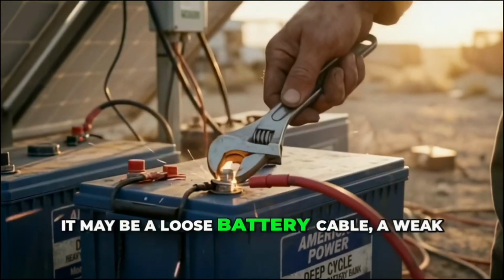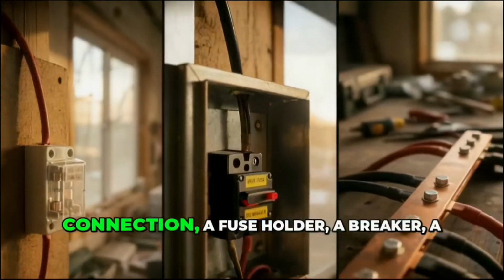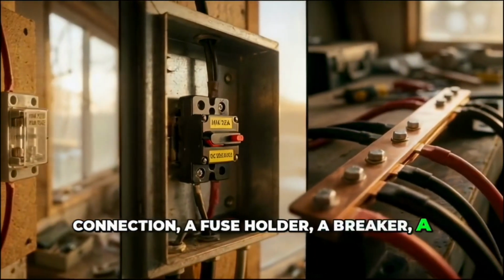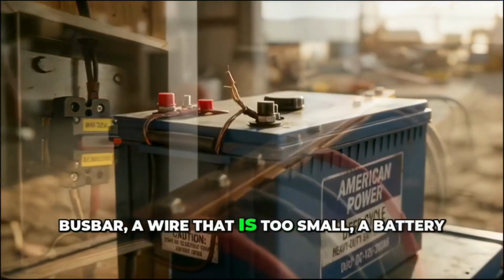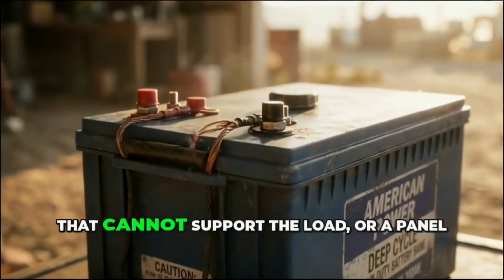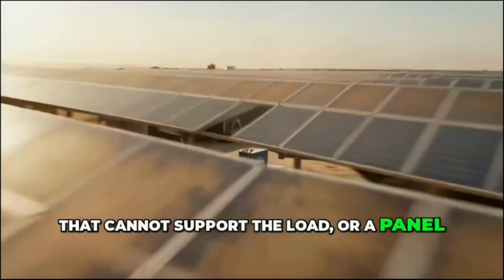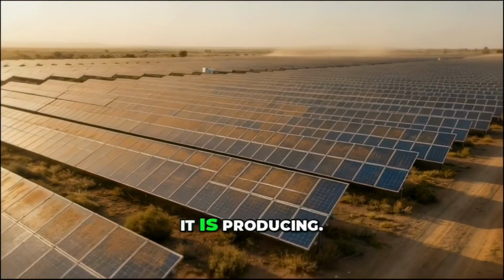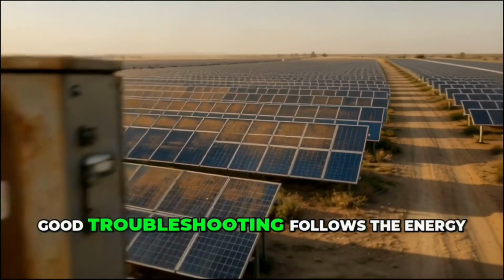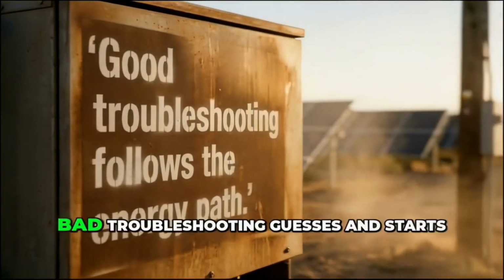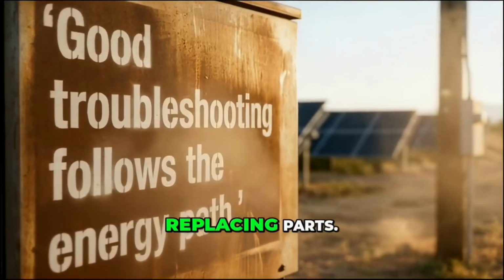It may be a loose battery cable, a weak connection, a fuse holder, a breaker, a bus bar, a wire that is too small, a battery that cannot support the load, or a panel array that is not producing what you think it is producing. Good troubleshooting follows the energy path. Bad troubleshooting guesses and starts replacing parts.